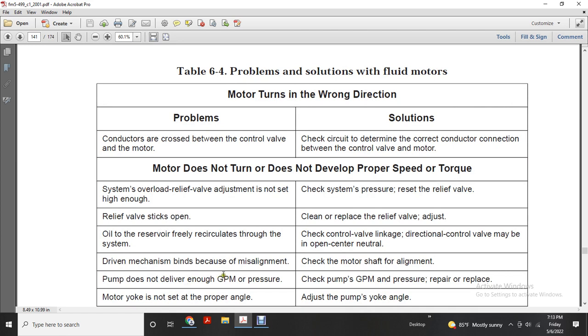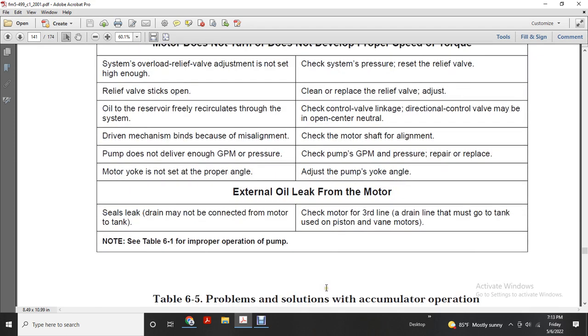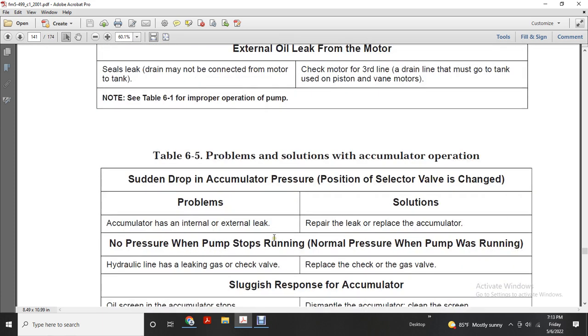Pump does not deliver enough gallons per minute or pressure. Check gallons per minute or pressure. Repair or replace. Pump yoke is not set at the proper angle. Adjust pump yokes. External oil leak from the motor. Seals leak, or the drain may not be connected from the motor to the tank. Check the motor drain line, which must go into the tank. Using piston and vane motors, see table 6-1 for improper operation of pump.